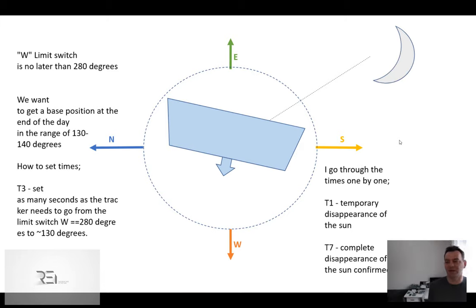If it disappeared, you wait the T1 time because maybe it's just the middle of the day with a lot of clouds. That's why the T1 parameter should be as big as possible. Then you confirm that using the T7 parameter.